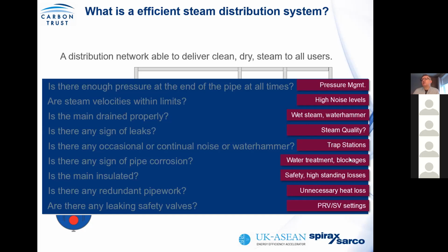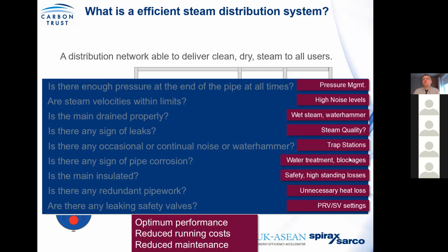And safety valves, what we find is that you have recommended pressure control, but again, where you have poor quality steam, you may find that the pressure control valves can't achieve optimum control. And you might find that safety valves are starting to leak or pass. And again, that's an indication of an ineffective system. So what we're looking to do is get optimum performance, reduce running costs, and reduce maintenance. And in doing so, you could find that the efficiency of your system will increase significantly.